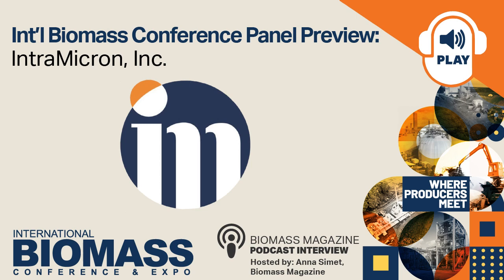Very well explained. So, Paul, what do you think sets the SourCat system apart from others? So I think the biggest distinguishing feature, and when we went to develop it, surrounds how simple the process is based on what it does. If you look at a lot of the catalytic processes to remove elemental sulfur, they either rely on bacteria, which can be temperamental, or they're multi-step processes. We have a single-step gas treatment process where we can selectively convert that hydrogen sulfide into elemental sulfur.